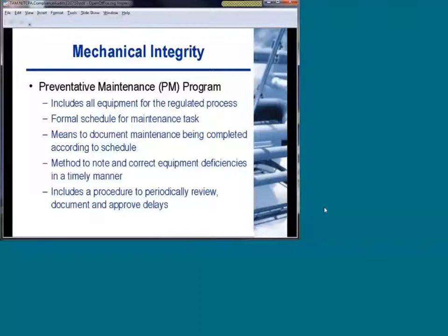So as I said, when I walk in to audit a PM program, I know, say, a compressor, you're going to have an oil draining, you're going to do daily logs, maybe monitor suction and discharge pressure, you may monitor temperatures, you may change filters annually, and you're doing a vibration analysis every 6 months to annually. So I'm keeping this in mind and looking at that schedule to see if I'm seeing these tasks on there. I then pull a maintenance guy and say, let me look into your computerized maintenance system. Have him walk over there. I ask him, okay, a compressor, I know you need so-and-so task. Can you pull a compressor? Let me see the history in your work order system, that these tasks are being completed according to the schedule and closed out. And I'm looking at that history in the PM program itself.